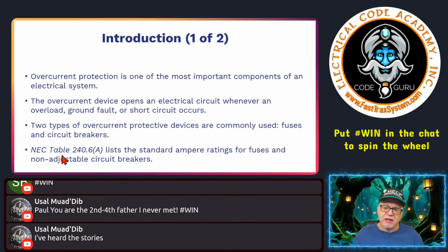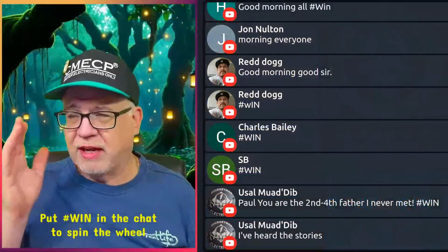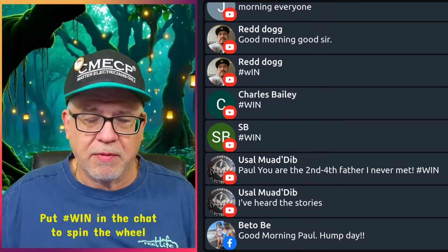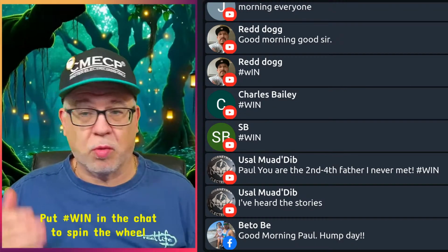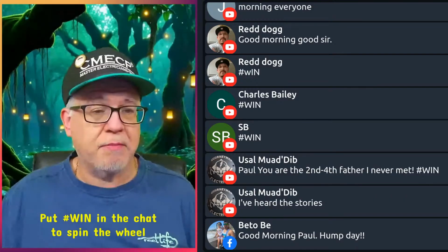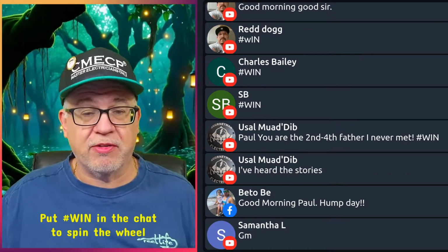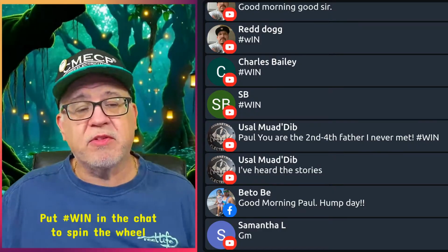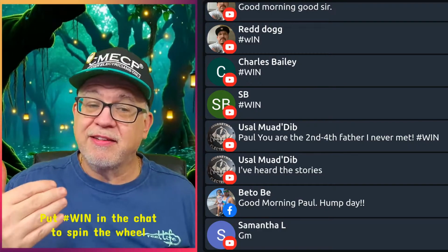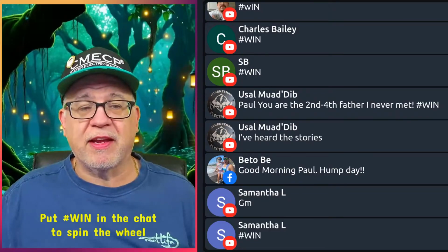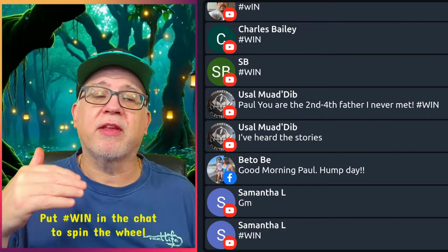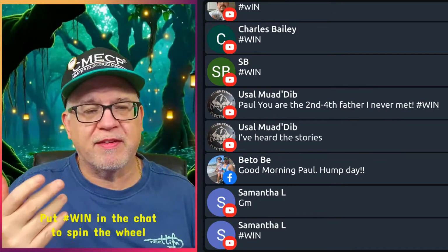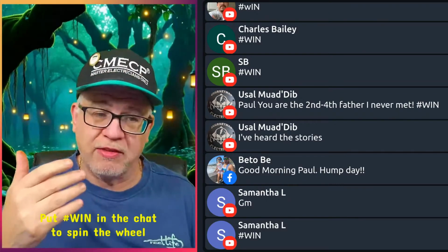Okay. So NEC Table 240.6(A) lists the standard ampere ratings for fuses and non-adjustable circuit breakers. So most of those circuit breakers that you're going to have in your panels in the houses, stuff that you deal with, are going to be non-adjustable. It's a 20 amp, it's a 15 amp, it's a 30 amp. You can buy non-standard types of circuit breakers. You've got standard in 240.6(A), and then don't lose sight that you can use non-standard. Now, when the code is going to reference things like 240.4(B), where we can go to the next standard size, then that's when you go to 240.6(A), because you can always go to the next non-standard size that may be less.